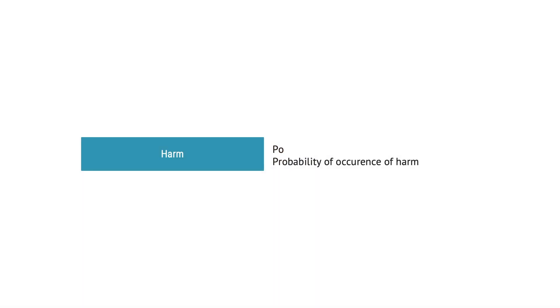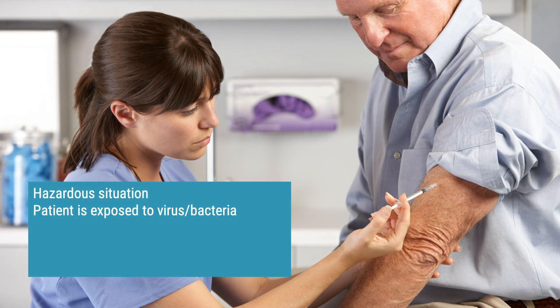When we estimate risk, it is the probability of occurrence of harm — or just PO — that we are looking for to type into our hazard traceability matrix. The probability of occurrence of harm is in turn dependent on the probability of occurrence of the hazardous situation, but they are not the same because not every hazardous situation leads to harm. In this picture, a patient receives some kind of injection. As soon as you puncture the skin, a hazardous situation occurs — the patient is exposed to a virus or bacteria.